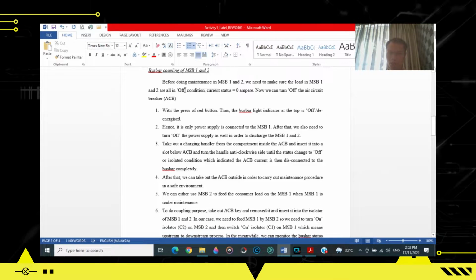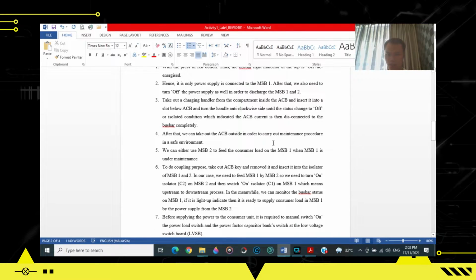Now for the bus bar coupling, MSB1 and 2, well, it's like doing a maintenance in the MSB1 and 2. So we make sure the load in MSB1 and 2 are off, and the current status is 0 ampere, so there's no current flow. So now we can turn off the ACB air circuit breaker. Press the red button, and the bus bar light indicator of red, yellow, and blue will be turned off and de-energized.